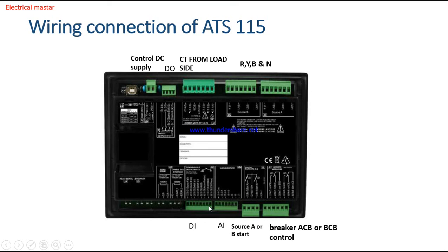Here you can connect the digital input, the configurable input. This is for the analog inputs, and this is for the starting command for the two sources, like start A and start B. It goes to the diesel generators. And here you have to connect the control for the ACB or BCB closing. The contactor in that panel you have to connect from here. So that is the wiring connection.